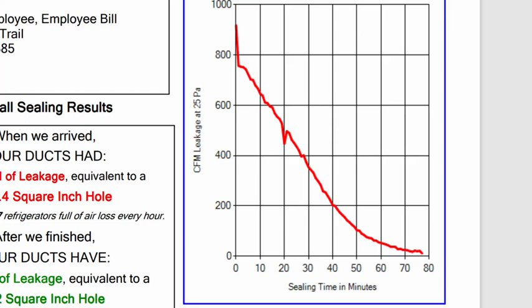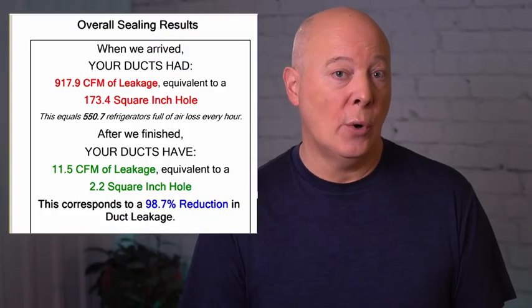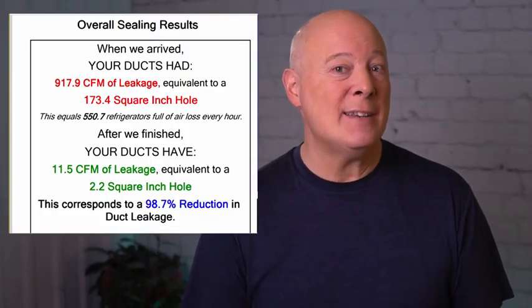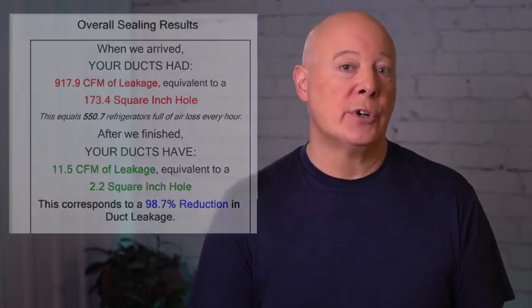The crew did some pre-sealing by hand, focusing on the bigger accessible gaps in the basement area. The pre-sealing reduced the leakage down to about 750 CFMs. That shows up on the graph as this steep drop in the first minute. It was actually over an hour of pre-sealing done in between the initial pre-seal test and when sealant started getting injected. They then let the machine do its thing for the next 75 minutes. They stopped at 11 CFMs, equal to a 2-inch hole, for a very impressive 98.7% reduction in return side leakage.